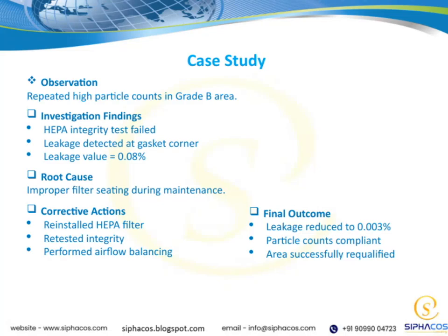In our final outcomes, I'm pleased to report that leakage has been reduced to an extremely low level of 0.003%. This means the particle counts are now fully compliant with the required standards, ensuring a safer, cleaner environment. We also successfully requalified the area, confirming that all systems are functioning as intended.